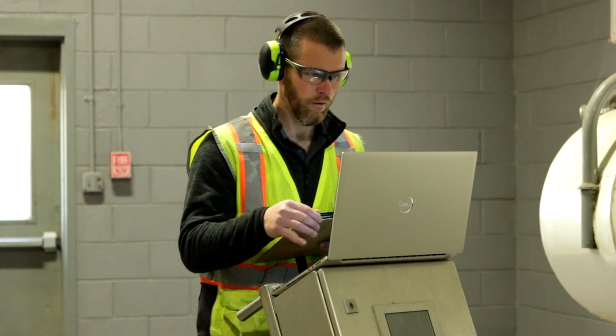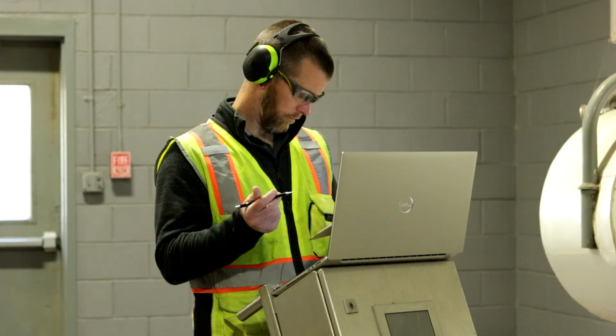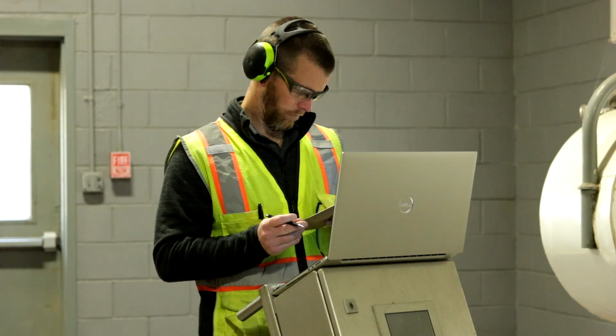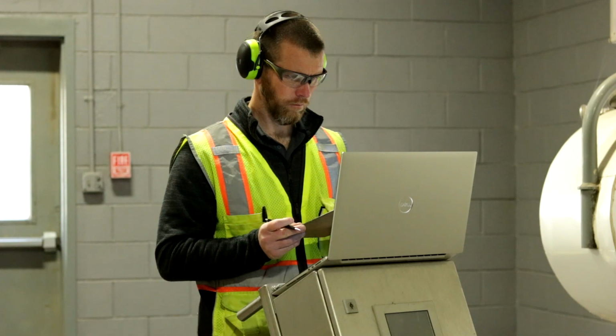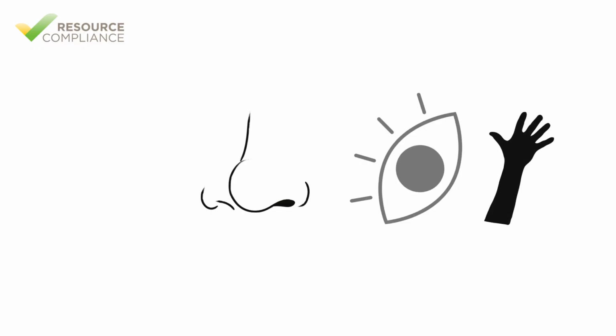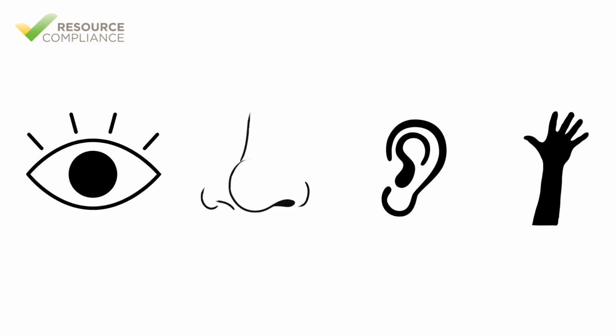It is completely acceptable to utilize technology when performing a system log. Employing web-based checklists can improve efficiency, organization, and provide valuable insight. However, a system log should rely on the operator's senses. Sight is critical for reading gauges and recognizing hazards. Smell is used to identify leaks, especially in ammonia systems. Touch can be employed to assess temperature. The use of hearing can alert an operator to an abnormality, such as a loose belt or bad bearing.